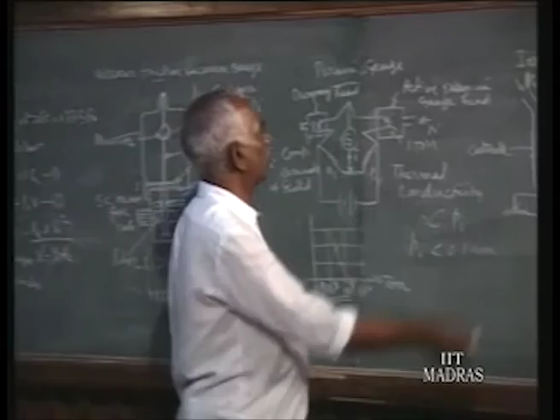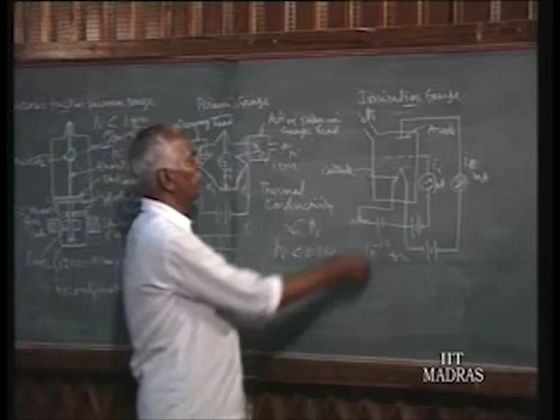The last method for the measurement of vacuum is the ionization gauge. The Pirani gauge range goes down to 10 to the power minus 3, but here we are going to 10 to the power minus 10 torr. It's a very high range. The principle is like this. It is somewhat like a triode electronic tube. It resembles an electronic tube, where you have a cathode and its own heating circuit.